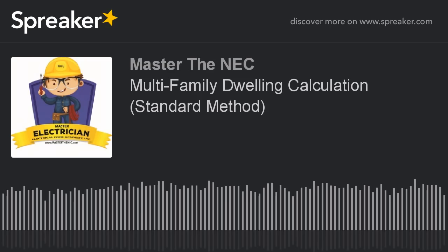That gives us 60,750. Now, we're going to write that right underneath the general lighting and receptacle under the service column, just under the 47,700. We're going to write 60,750. Now, right next to it in the neutral column, we're going to put 0 because these were 240 volt loads. There is no neutral, so we put nothing there.